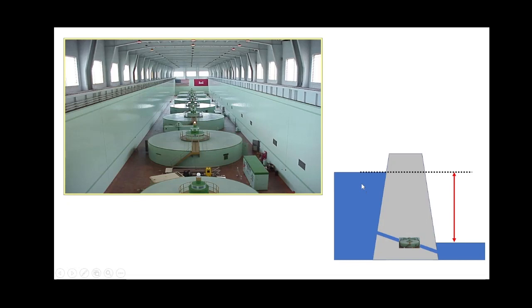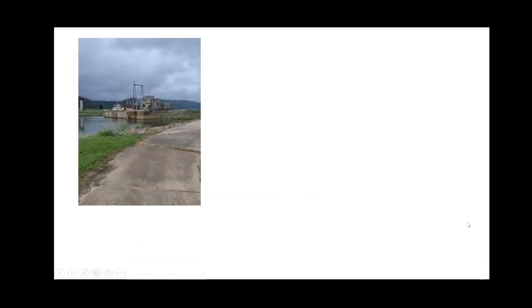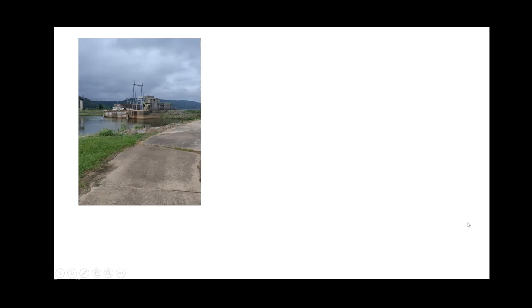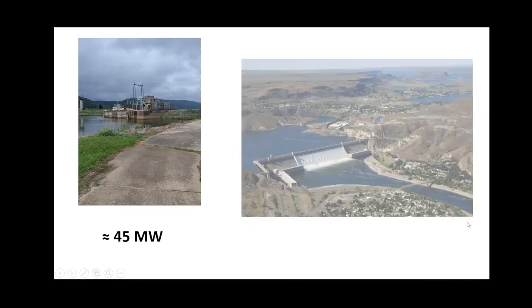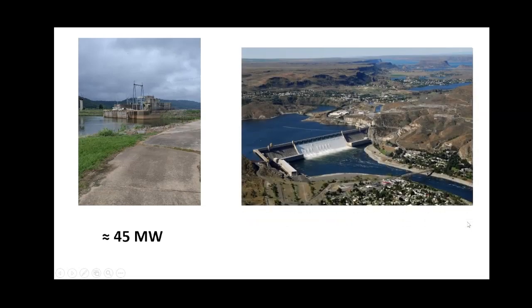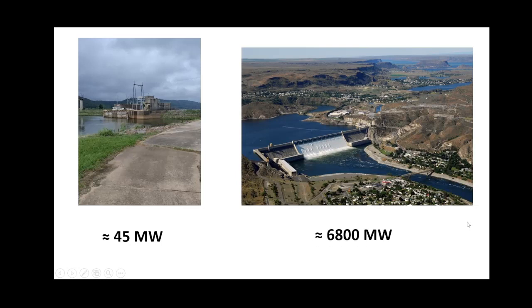Upstream of the dam is called headwater. Downstream is called tailwater. And the difference between those two is called the head differential. When sizing a power plant, that determination is made by how much flow and head differential is available. We can have a relatively small power plant like this one on the Arkansas River with a capacity of about 45 megawatts, or very large power plants like Grand Coulee Dam on the Columbia River with 6,800 megawatts.